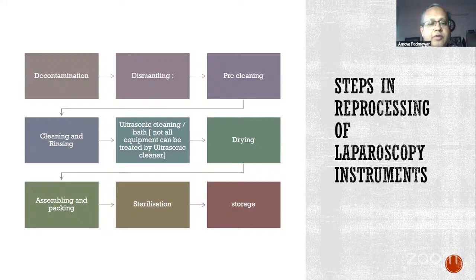After this, if your center has something known as an ultrasonic cleaning bath, it is a great adjunct to the whole assembly, because ultrasonic agitation of fluid with the instruments therein will dislodge all the biological and organic material from its joints and make them clean. After doing all this, you have to dry them. The instruments have to be dry, because if you autoclave them, the solution is going to harbor some spores and some organisms, especially atypical mycobacteria. So drying of them is very, very important.